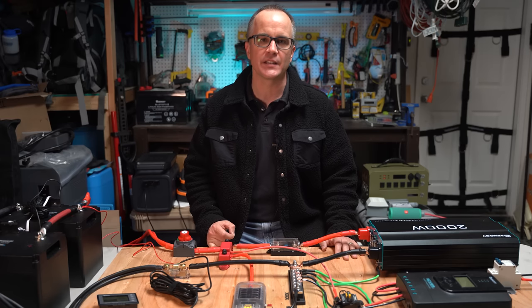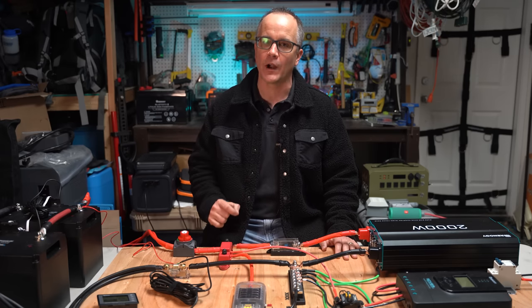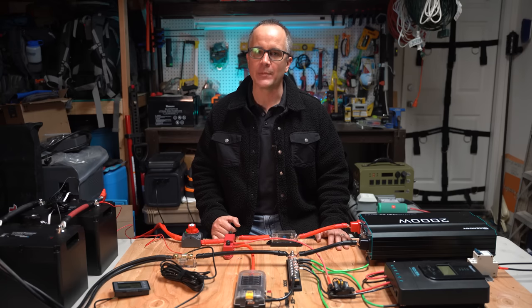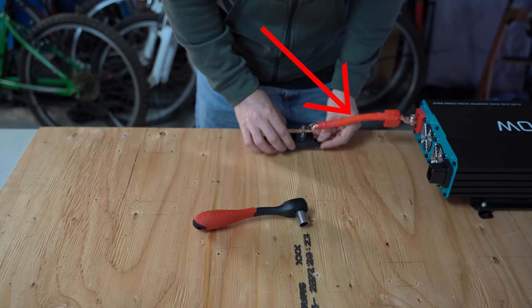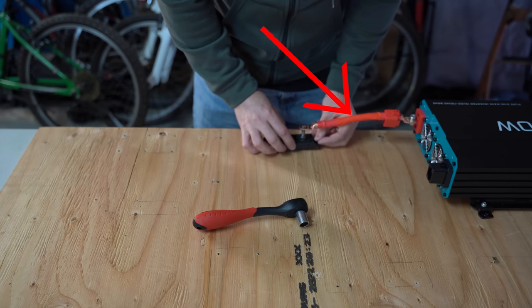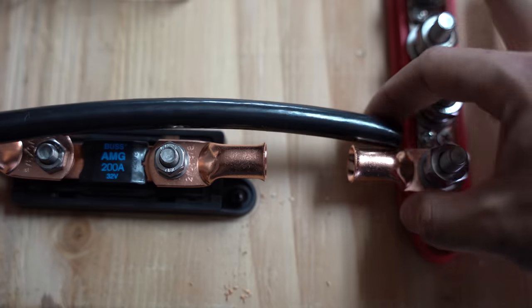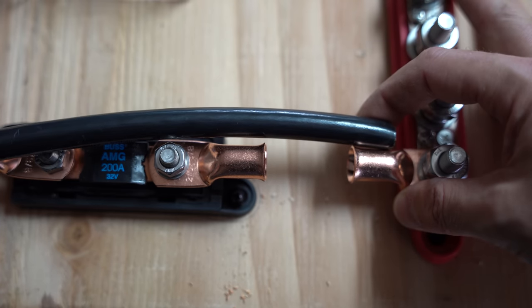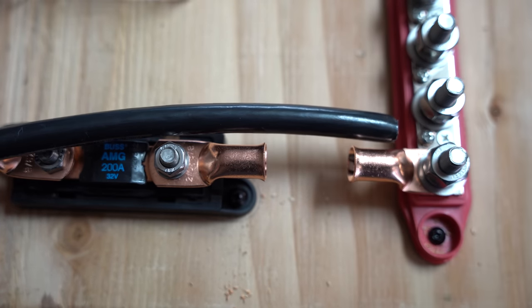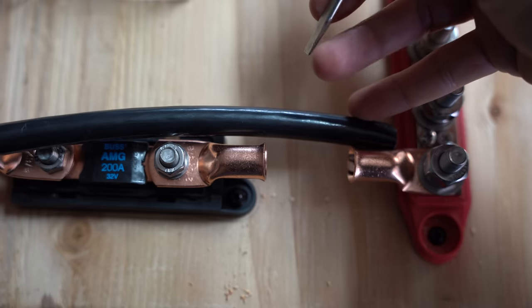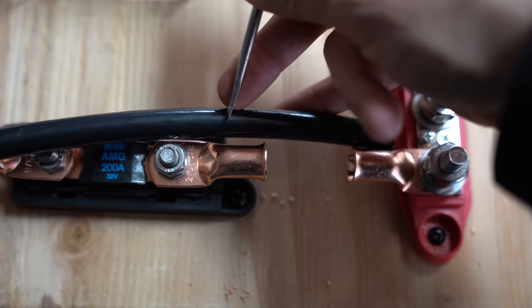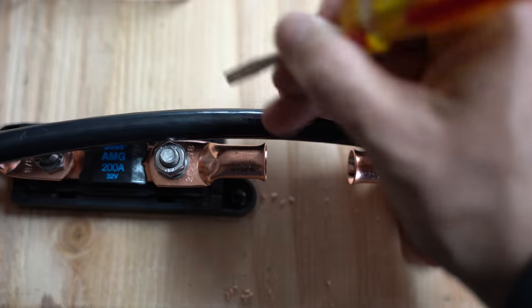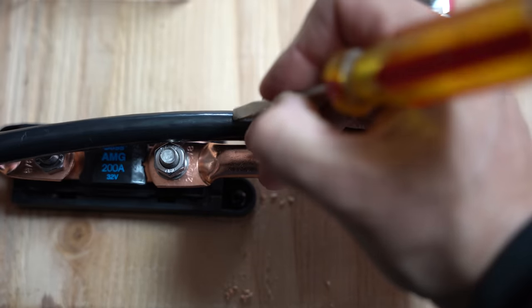Remember earlier when we discussed the amount of current that this inverter will require? Based on a formula, we determined that we need wiring that can handle 196 amps. The wire that we have here is 2-aught gauge and can handle 200 amps. As shown here, I put the cable lugs on the post of the components we're going to connect together. This serves two purposes. First, I can make sure I'm getting the correct cable lug, as some have different sizes based on what you're connecting to. Secondly, I can then measure the distance of the cable based on where these cable lugs are located.